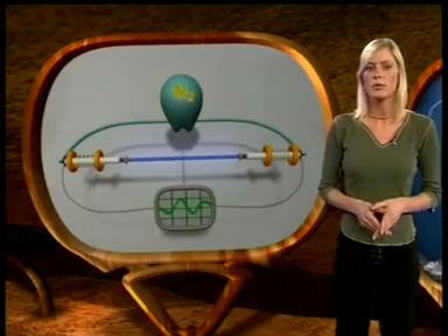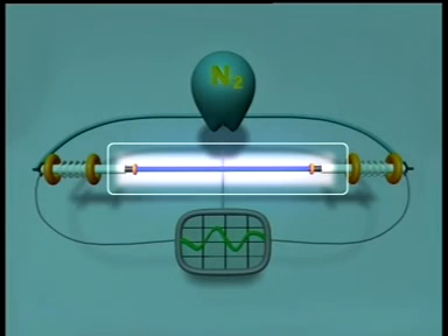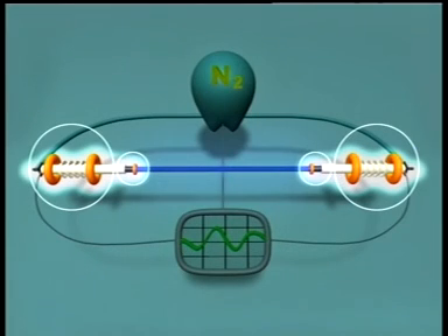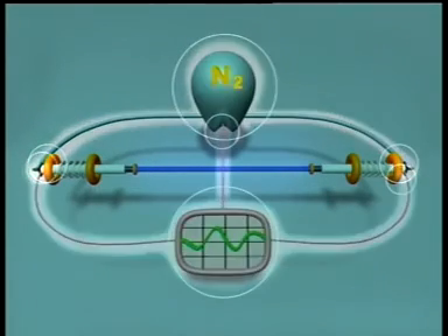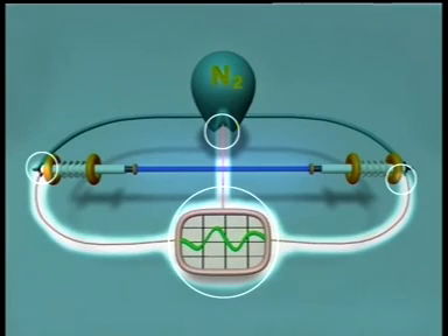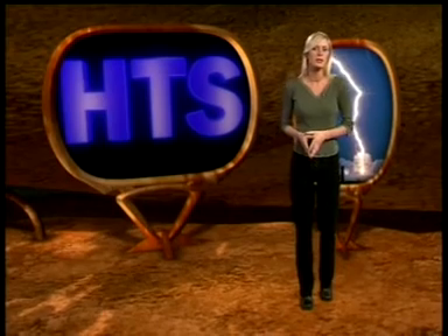The superconducting cable system has four main parts: the superconducting cable itself, termination in each end, a cooling system, and a monitoring system that observes the status of all components. This exciting new cable technology has some advantages that I'll describe later. The disadvantage, however, is the need to keep the superconductor cold. Although they're called high-temperature superconductors, they must be cooled to about minus 200 degrees Celsius, or 77 degrees above absolute zero temperature. The medium used in the NKT system is liquid nitrogen, which is cheap and exists all around us.